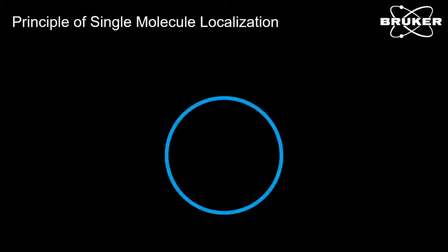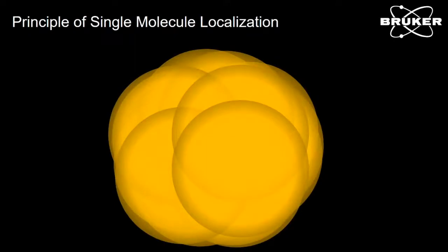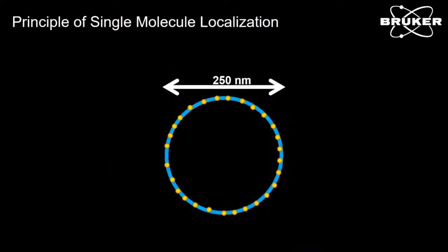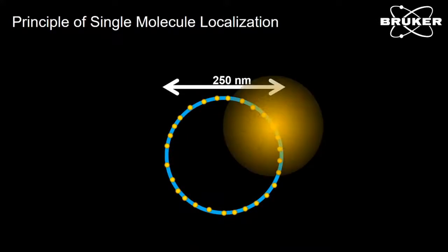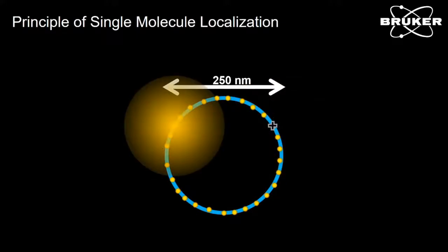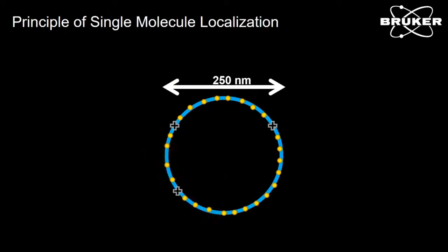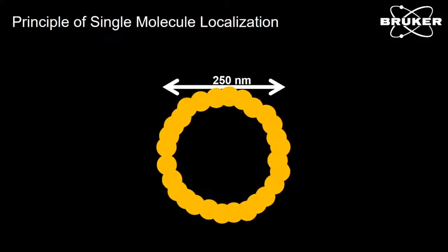So how does that work? If you have an object in a cell that's below the diffraction limit of light — say this tubule, 250 nanometers in diameter — we can label this with fluorophores evenly across its surface. If you look at the ensemble fluorescence, we get this diffraction-limited blur and we can't localize it. However, if we have a way to stochastically activate one or two molecules at a time and isolate these point spread functions, we can use our SRX software to very accurately localize the center point of that point spread function. Then we can activate more molecules, localize them, and repeat until we have all the molecules registered and localized — building an image below the diffraction limit of light.